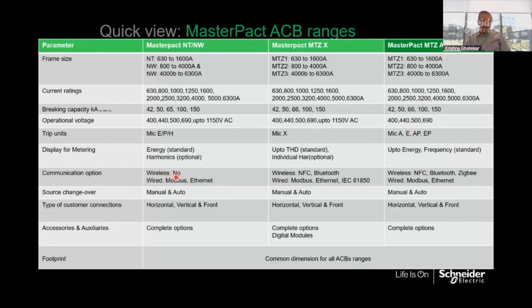Communication: there is no wireless in this. You can have wired with Modbus or Ethernet. In MicroLogic X, you have NFC and Bluetooth as wireless, and wired you can have Modbus, Ethernet plus IEC 61850, generally if you want to do substation automation. Whereas in MTZ Active, you not only have NFC and Bluetooth, plus Zigbee also for connectivity with a Pass gateway, and wired is Modbus and Ethernet. Dimension wise, in accessories, it is similar.